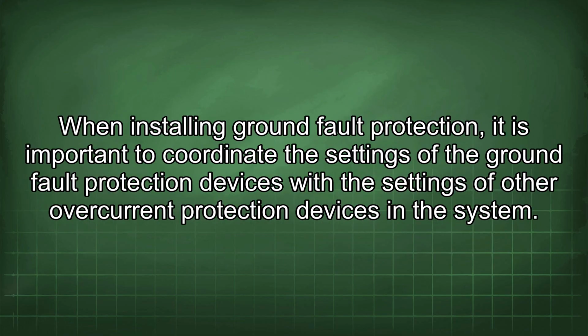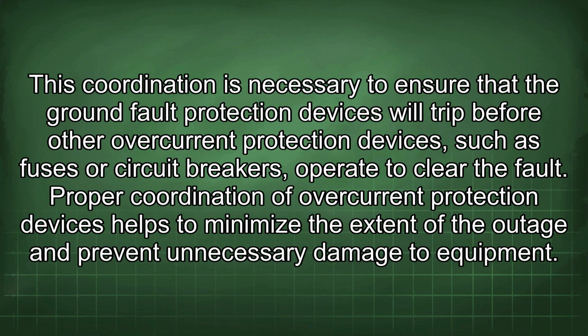When installing ground fault protection, it is important to coordinate the settings of the ground fault protection devices with the settings of other overcurrent protection devices in the system. This coordination is necessary to ensure that the ground fault protection devices will trip before other overcurrent protection devices, such as fuses or circuit breakers, operate to clear the fault. Proper coordination of overcurrent protection devices helps to minimize the extent of the outage and prevent unnecessary damage to equipment.